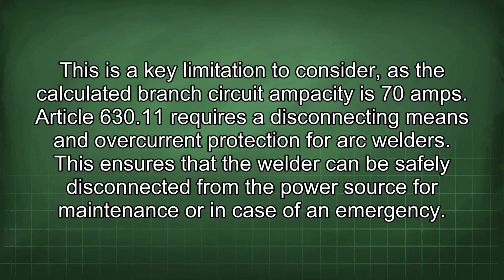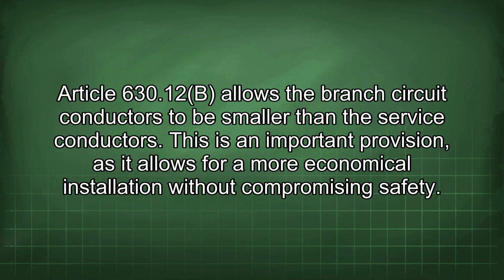Article 630.11 requires a disconnecting means and overcurrent protection for arc welders. This ensures that the welder can be safely disconnected from the power source for maintenance or in case of an emergency. Article 630.12(B) allows the branch circuit conductors to be smaller than the service conductors. This is an important provision, as it allows for a more economical installation without compromising safety.